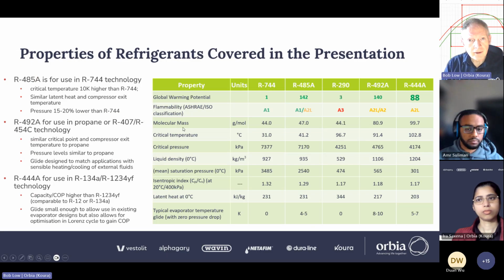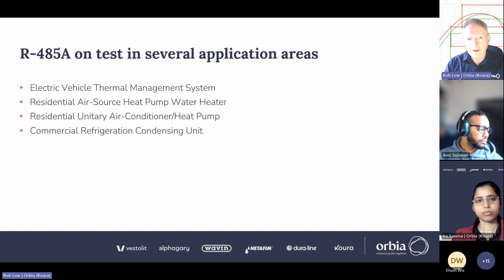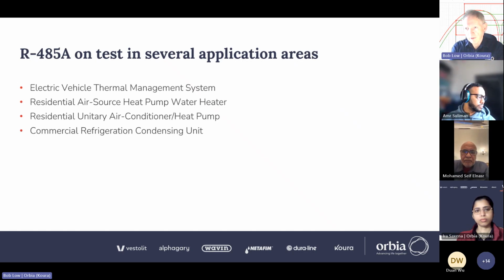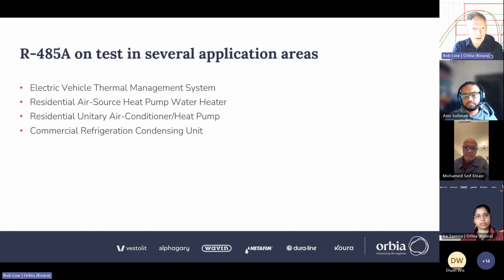I'm going backwards about that. So coming on first to 485A. The point of this fluid is to exploit the developments of CO2 technology and to exploit the good features of a CO2 cycle, but to ameliorate the bad features of CO2. And what are the bad features? Extremely high operating pressure, extremely high compressor exit temperature, and rapid degradation of cycle efficiency as the ambient temperature goes much beyond the critical temperature of CO2 itself, which is 31 C, of course. So the blend is 69% CO2 and it's 21% R32 and 10% of R1132A. It's non-flammable. Its critical pressure is actually similar to that of CO2, but its critical temperature is 10 K higher. And that makes all the difference.